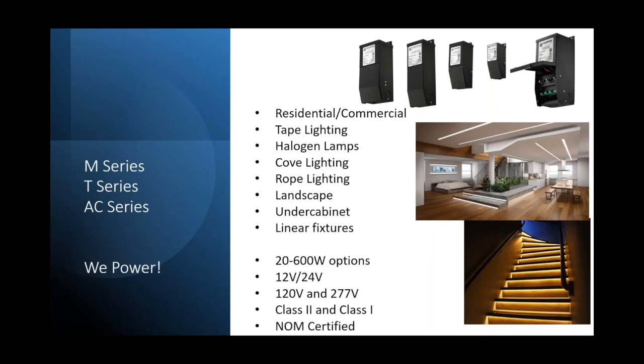We offer our magnetic transformers in multiple wattage options, ranging from 20 watts all the way up to 600 watts. We also offer a multi-tap system, used with our T series, which allows you to keep the Class 2 rating if needed, but also at a higher wattage. We offer different voltages, 12 and 24, available in a 120 input or 277 input option. We have the transformers Class 2 or Class 1 rated, and the M series and T series are all NOM certified currently.